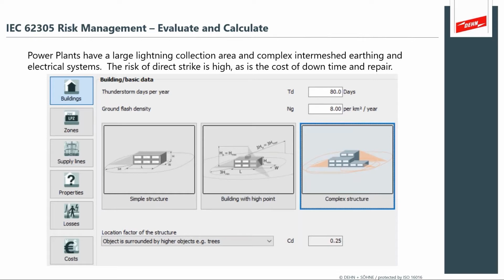So that large collection area also imparts itself in the risk calculation. In the IEC 62305 system of lightning protection standards, it starts with an evaluation of your risk. And a power plant has a high degree of risk. It's a large structure. It's a large interconnected structure. It has very valuable power generation transformer systems, transformers themselves that will have very long lead times, and high value transformer type power generation systems. The risk of direct strike is high, as is the cost of downtime and repair.